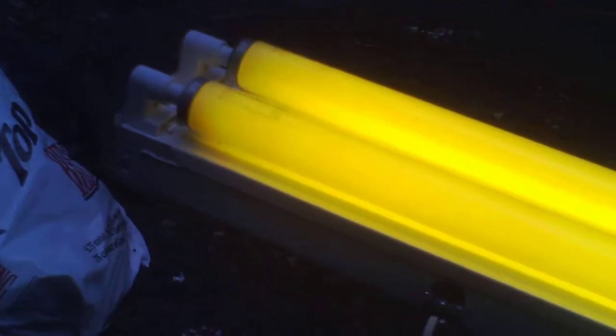This is my test fixture. It's a dual lamp F72T12 slimline fixture running gold lamp so it is normal for the things to appear yellow. You can see that, GTE Sylvania, these are old stock high quality lamps, gold, 55 watt. Because the 72 in the rating refers to the length of the lamp, not the power rating. T12 of course is the envelope, T12 or one and a half inch diameter.